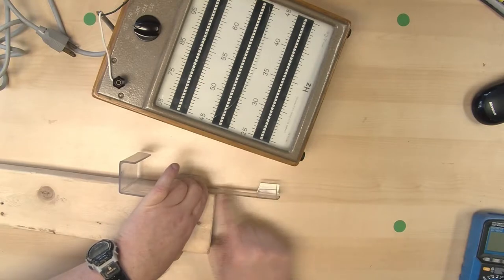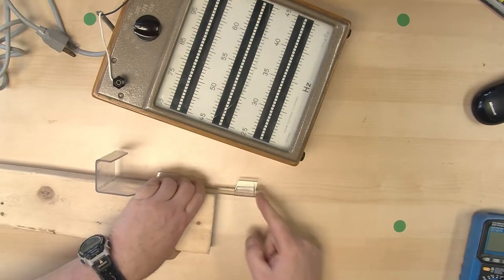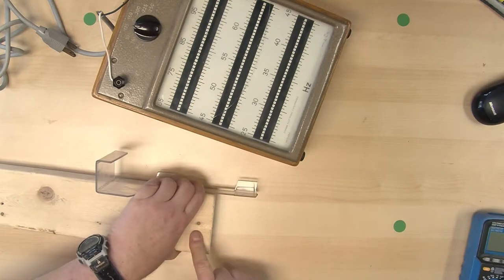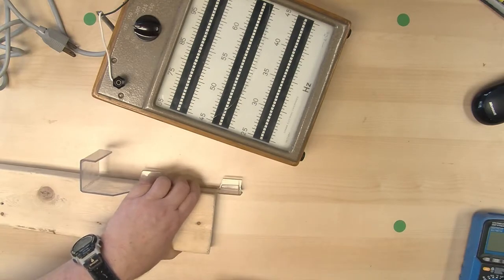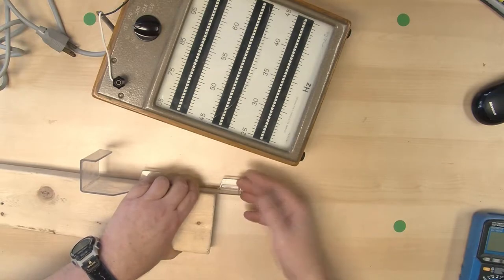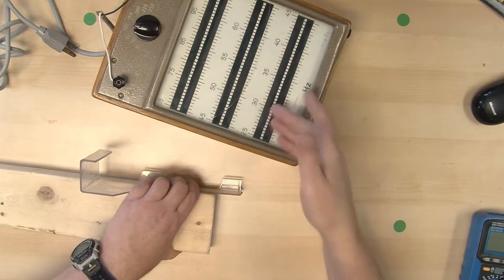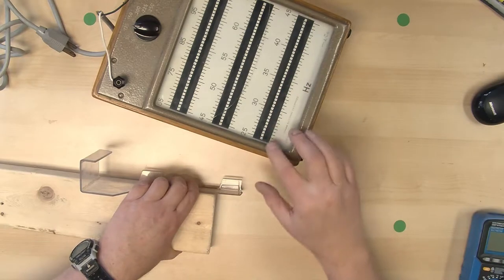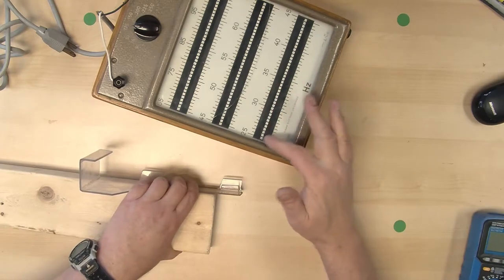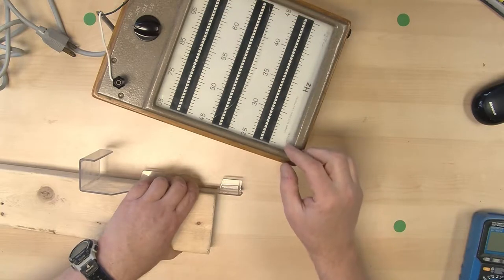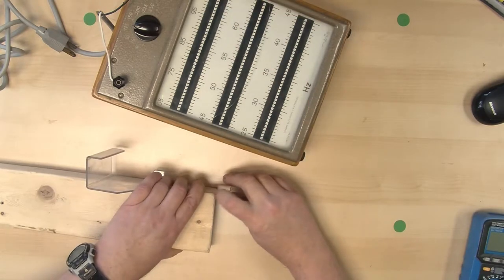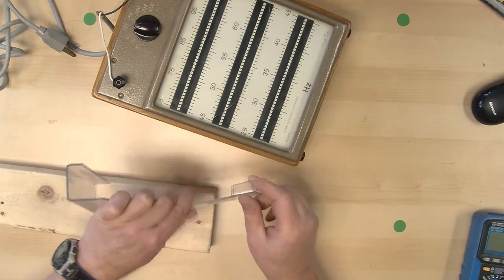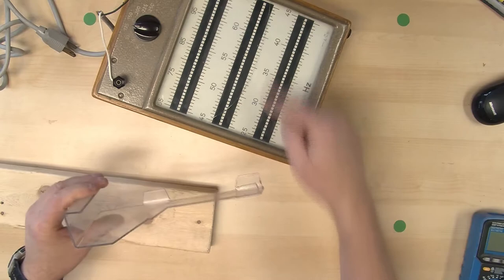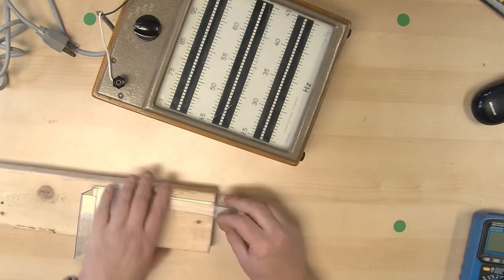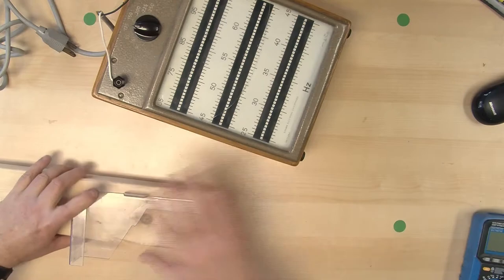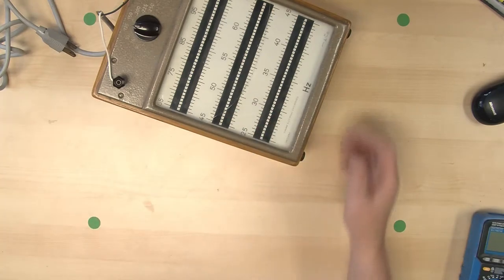And if I change the length by bringing it in, it will vibrate faster and faster. And that's really the principle behind the reeds here. You can sort of imagine that the lower frequency reeds are longer, the higher frequency reeds are shorter, and probably by grinding away at the material on the reeds, they can fine-tune the frequency of each reed during the manufacturing and calibration process. So that's the vibrating reed frequency meter.